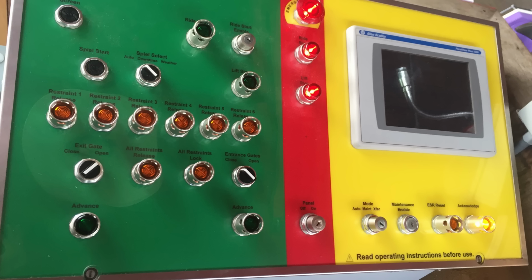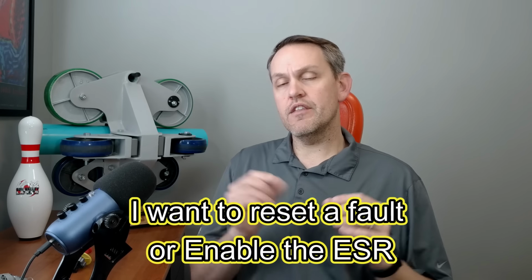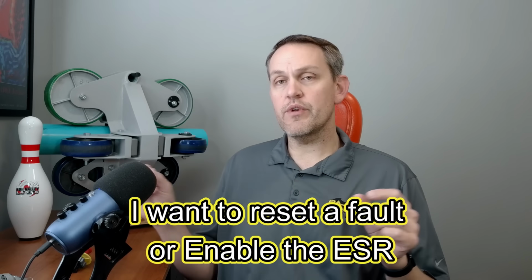Maintenance mode, again, is for maintenance personnel to come in and do things that the automatic mode can't do. Auto mode is the basic one. It has the ride start, lift hill start, dispatch, some exit gate controls, a bunch of the stuff we just talked about. Maintenance mode is where you can come in and say, I want to run those motors in reverse. I want to put a train away into transfer. I want to jog the lift hill. I want to open the brakes. It gives me individual control over most components in the ride.